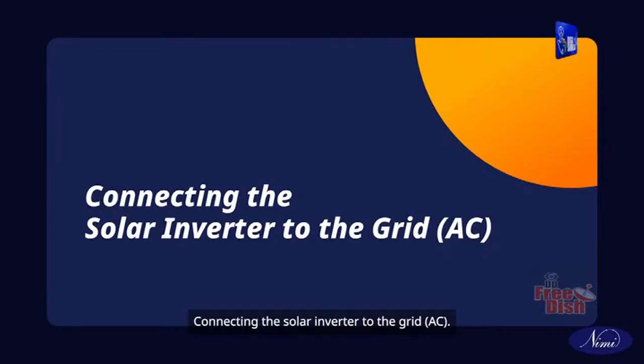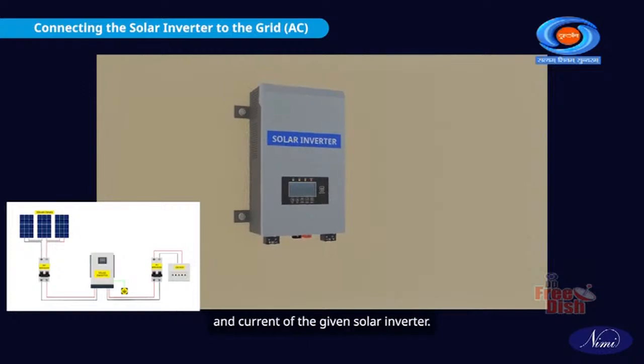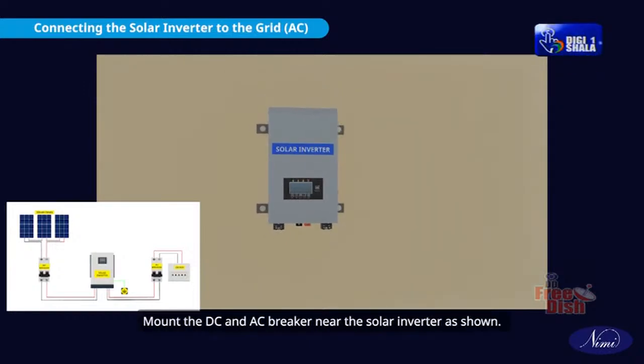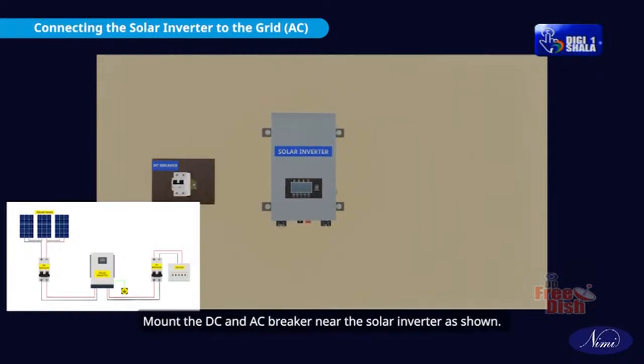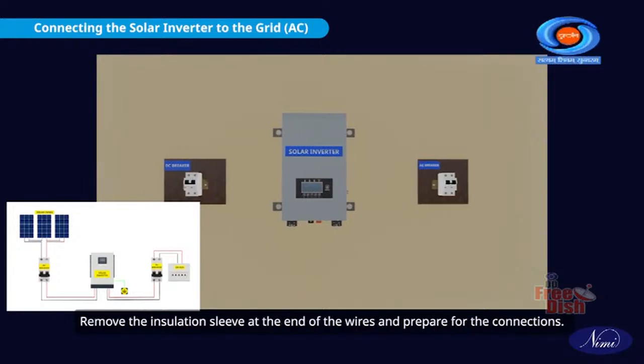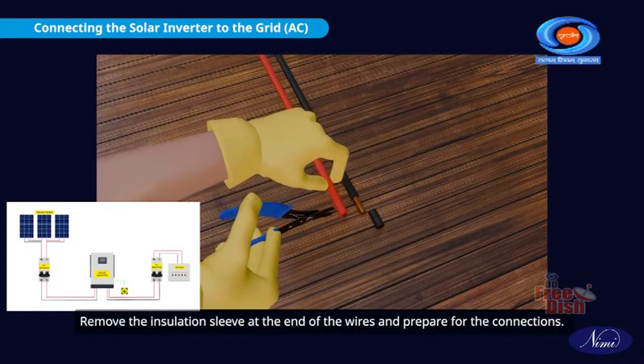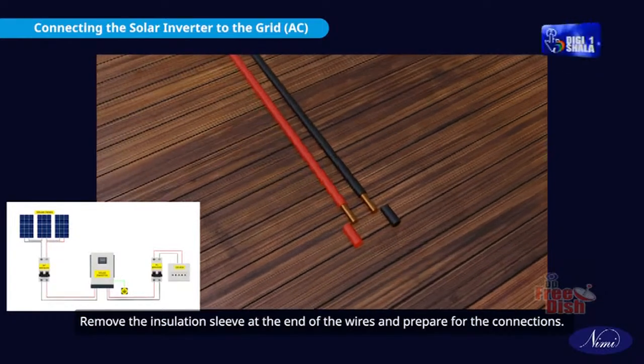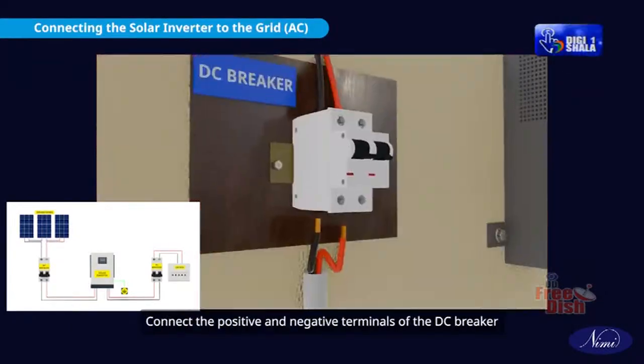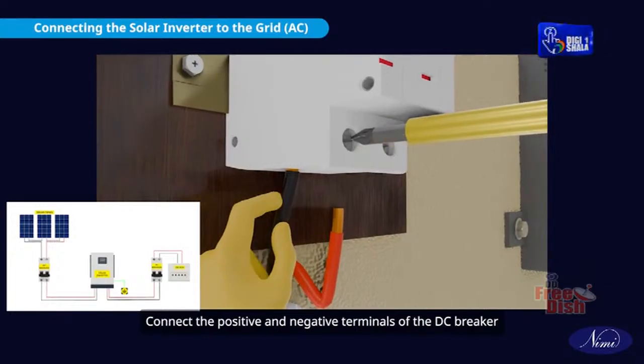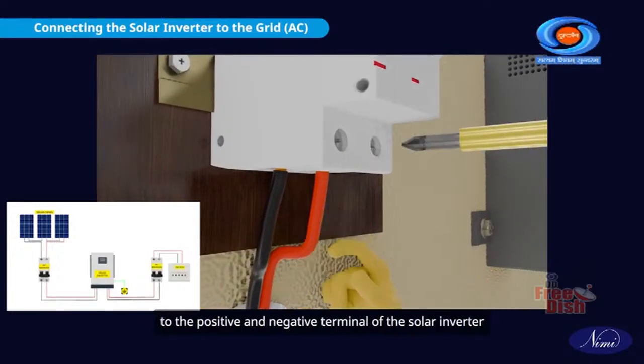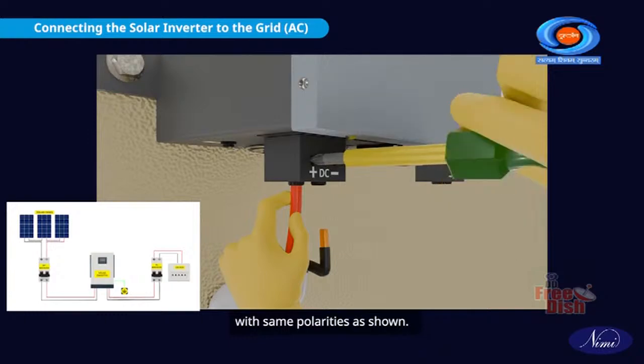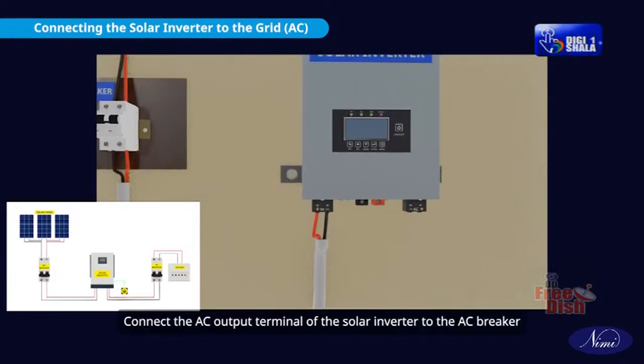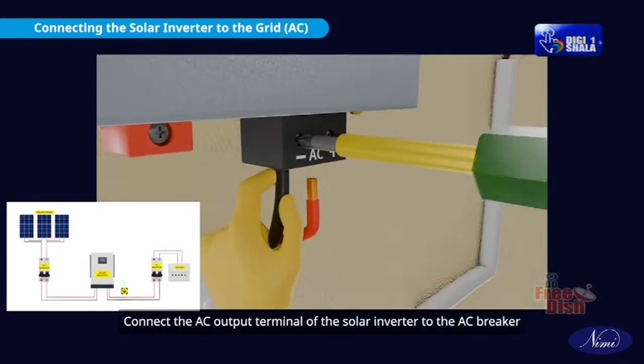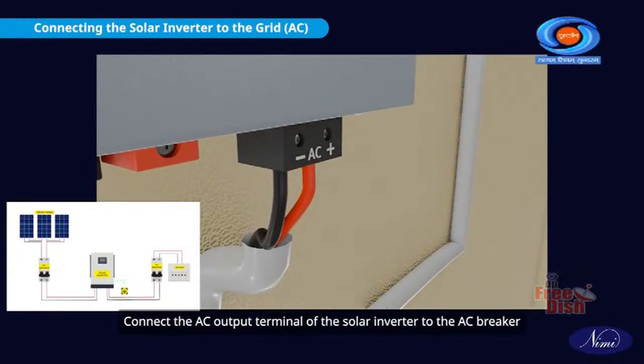Connecting the solar inverter to the grid AC. Refer to the user manual and note the rated voltage and current of the given solar inverter. Mount the DC and AC breakers near the solar inverter as shown. Remove the insulation sleeve at the end of the wires and prepare for the connections. Connect the positive and negative terminals of the DC breaker to the positive and negative terminals of the solar inverter with the same polarities as shown. Connect the AC output terminal of the solar inverter to the AC breaker.